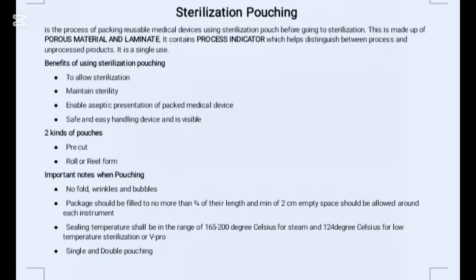Sealing temperature shall be in the range of 165 to 200 degrees Celsius for steam and 124 degrees Celsius for low temperature sterilization or V-pro, because at the moment we are using the steam and the low temperature sterilization. So we are using two different materials. And in sterilization, it could be single or double pouching. This information is taken from SteriKing.